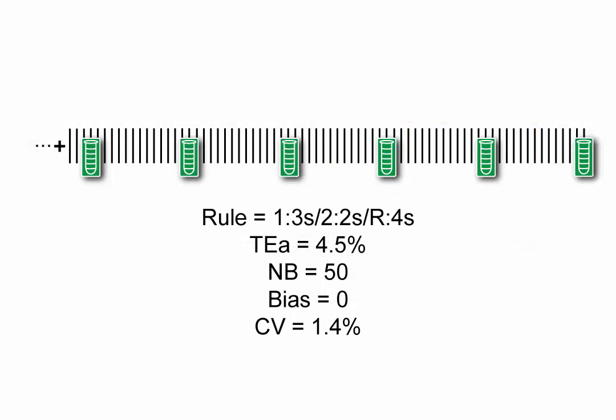The number of unreliable final results depends on the QC strategy, test method performance relative to the allowable total error specification, TEA, and the size of the out-of-control condition. The QC strategy is the QC rule, number of QCs evaluated, and number of analyte examinations between QCs, NB. Test method performance is the test method's bias and imprecision.